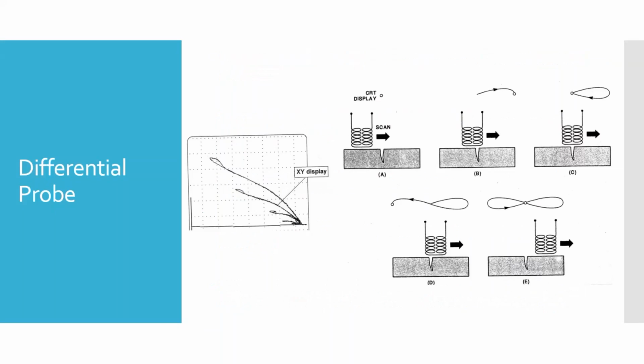So here's what a differential probe looks like. On the right you can see the wiring of it - as mentioned, it's two coils, wired in series but reverse wound from each other, so they induce opposite currents in one another. Those eddy currents are going to induce opposite currents in them.